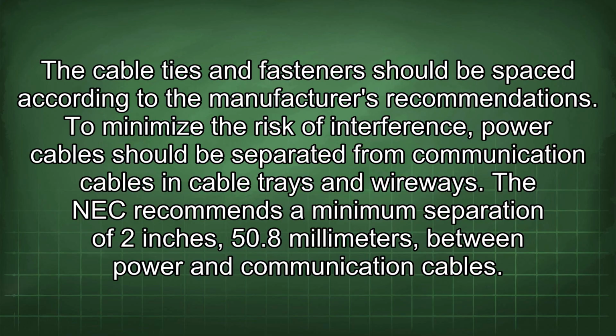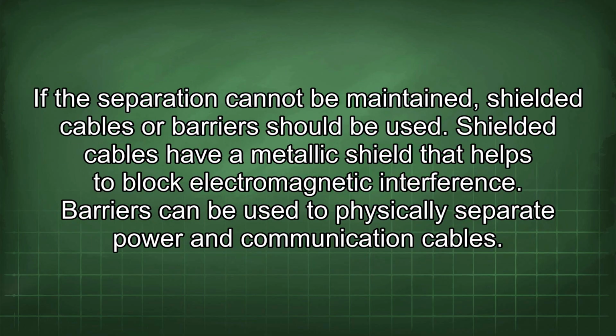To minimize the risk of interference, power cables should be separated from communication cables in cable trays and wireways. The NEC recommends a minimum separation of 2 inches, 50.8 mm, between power and communication cables. If the separation cannot be maintained, shielded cables or barriers should be used. Shielded cables have a metallic shield that helps to block electromagnetic interference. Barriers can be used to physically separate power and communication cables.